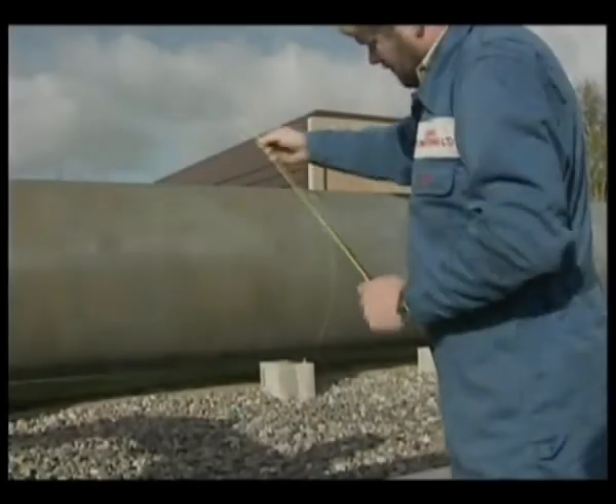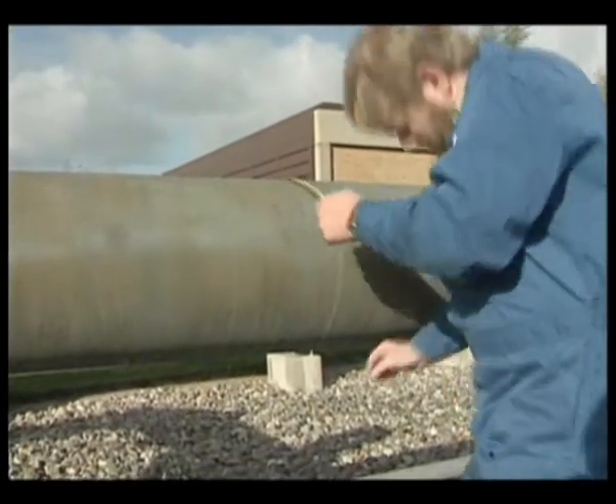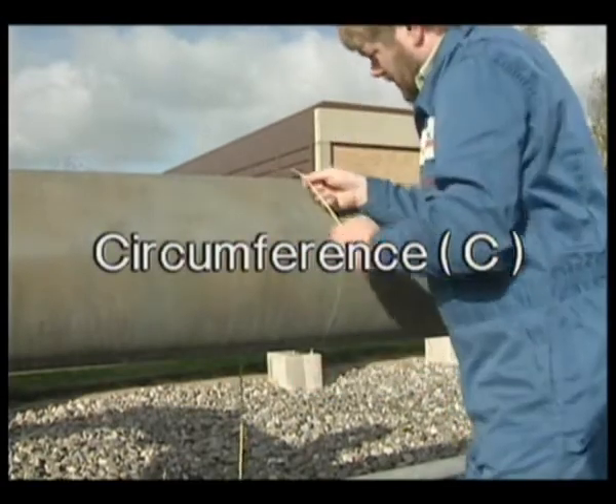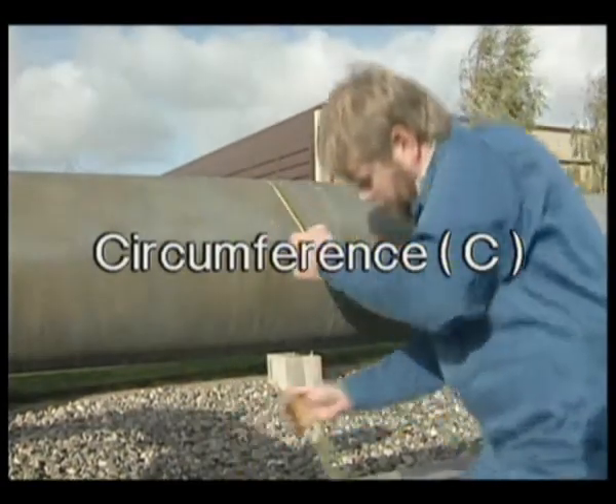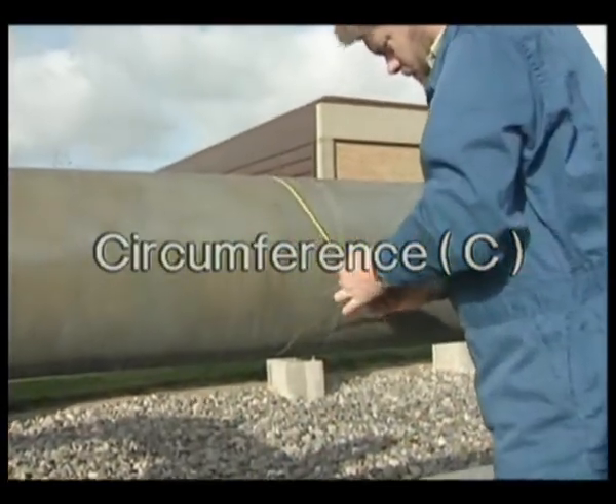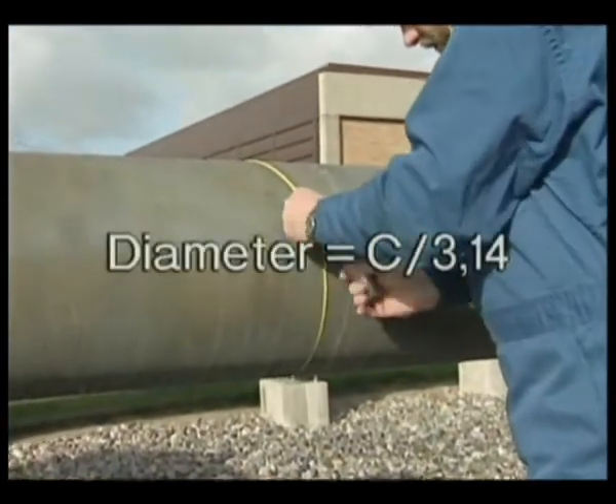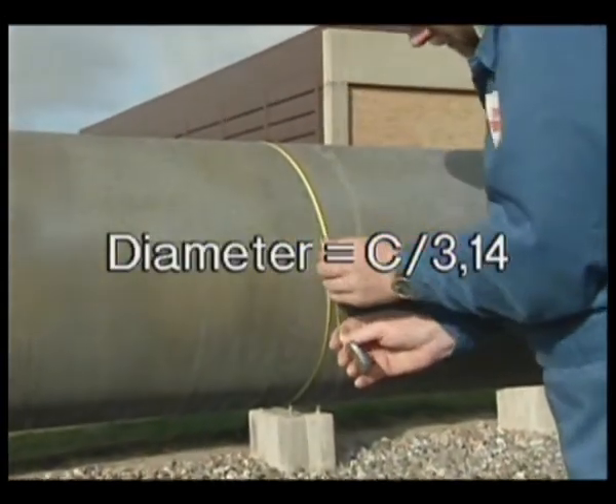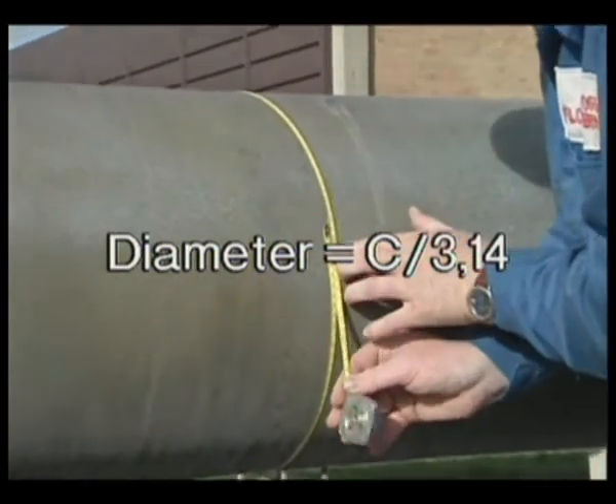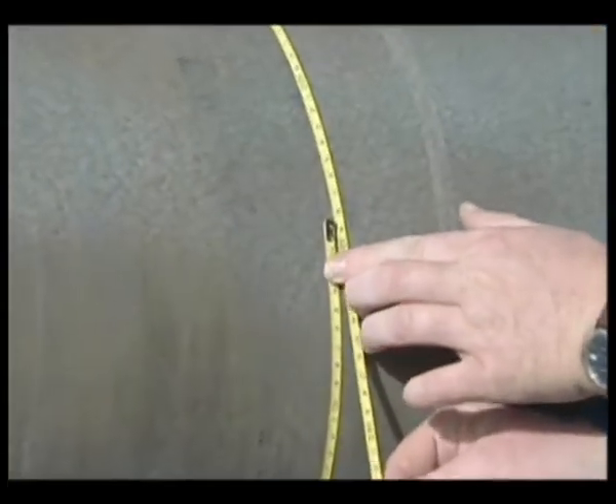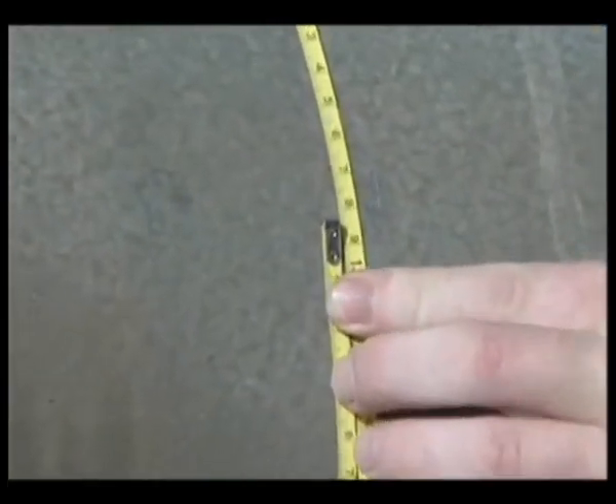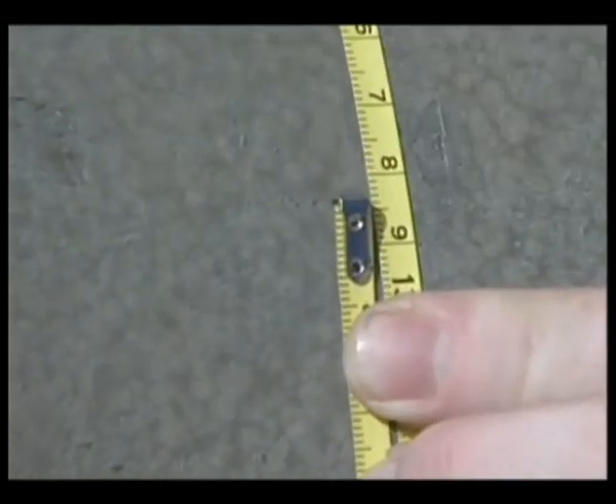To be able to determine the construction of the flow meter, we have to get some data on the pipeline. The data we need is the circumference and the pipe wall thickness. The pipe diameter can be calculated by means of the formula circumference divided by pi equals diameter. We'll now start constructing a meter on the supplied roll of paper.